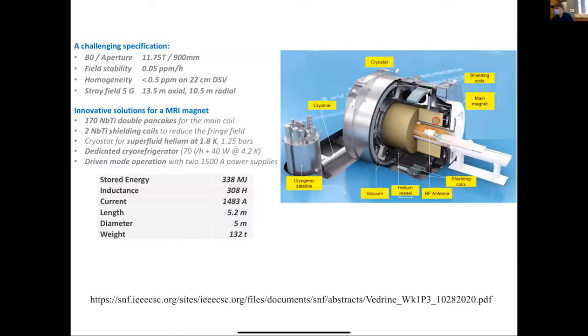Looking at the magnet's cross section, you can see the main magnet coil. There are also shielding coils going in the opposite direction to reduce what's called the fringe field — we'll discuss that shortly. There's also a small RF head coil visible for transmitting radio frequency energy.